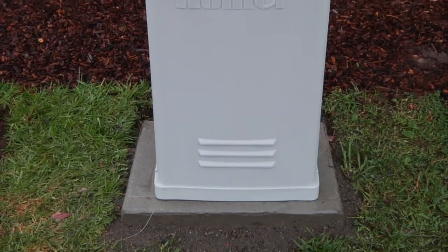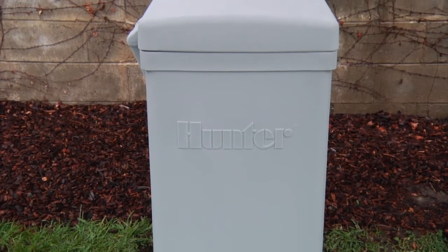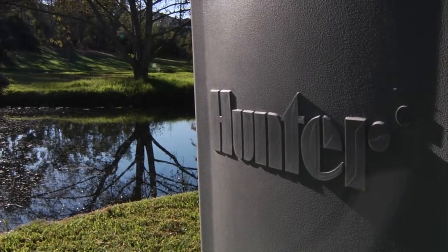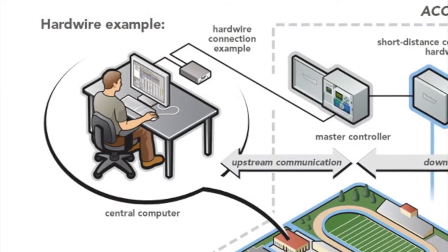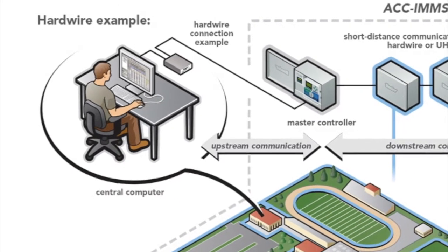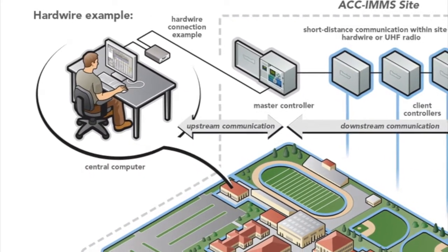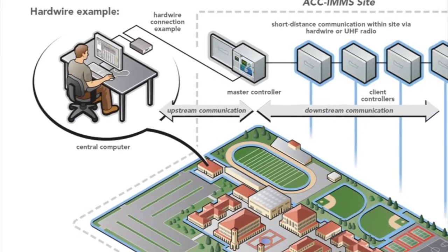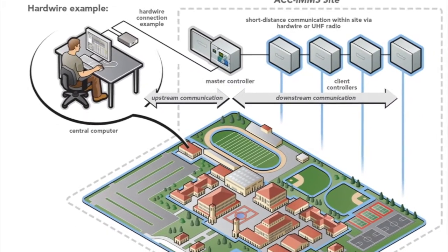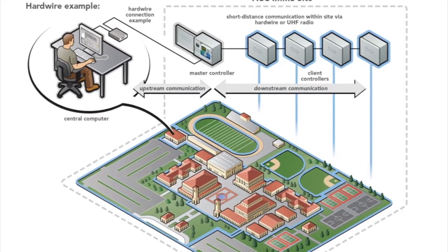Now when it comes to pedestal controllers, they're usually out in the open, and you might want to take into account any possible tree root growth down the road, as well as if you're in a low spot that may collect water even though your pedestal is a couple inches off the ground. That can make a big difference there. One of the last things is also communications. So if you'll be using a central system where you'll be communicating from a central computer remotely, you want to consider if you're going to be using hardwire, phone line, or an Ethernet cable, and that'll also dictate where the controller ends up going very possibly. So take those things into consideration before you select your location.